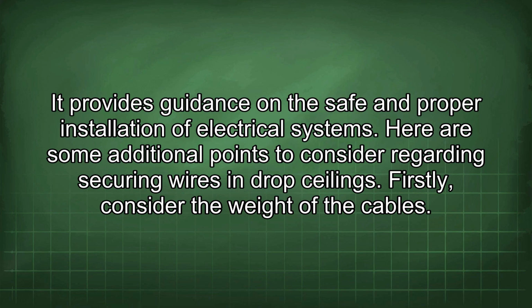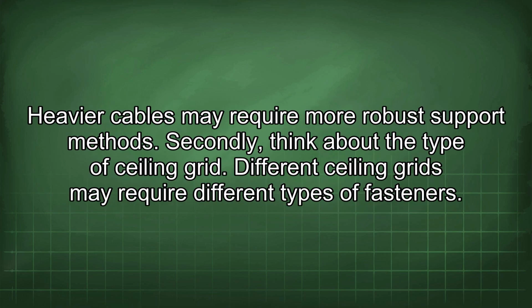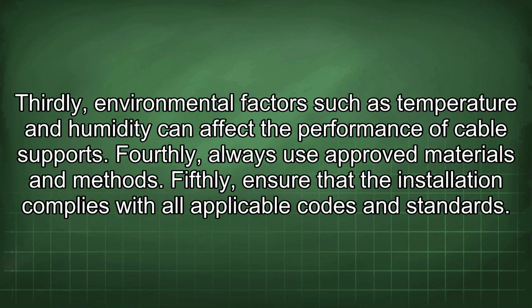Here are some additional points to consider regarding securing wires in drop ceilings. First, consider the weight of the cables, as heavier cables may require more robust support methods. Second, think about the type of ceiling grid, since different grids may require different types of fasteners. Third, environmental factors such as temperature and humidity can affect the performance of cable supports.